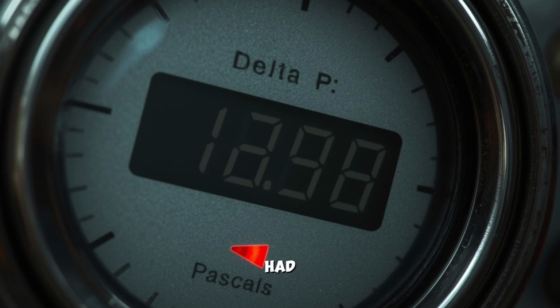The firmware update had altered the pressure control strategy in a way that amplified rather than compensated for the stack effect, particularly in the upper thirds of the affected buildings. Elevator shafts, which normally operate at near neutral pressure relative to the floors they serve, had become positively pressurized as the supply air volumes increased and return air pathways constricted.